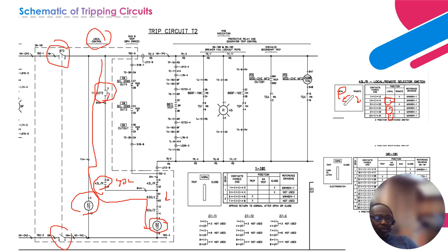And remember, I also told you that if there should be any problem with the density of the gas, that is the pressure of the gas, or density of the SF6 gas. The breaker utilizes SF6 gas as a quenching medium, a dielectric medium, because during the operation of the breaker, during either closing or contact parting, it creates an arc if a fault should occur. So that requires a dielectric medium, and SF6 is utilized to quench the arc, which supports the operation of the breaker.